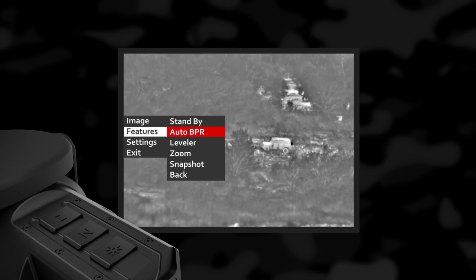Auto BPR, bad pixel repair function. This device has an automatic algorithm for clearing defective pixels on the screen. Attention: small objects on screen at a farther distance might be observed as 1-2 pixels and considered defective pixels by the algorithm. When observing objects at a long distance, please turn off the auto BPR function.